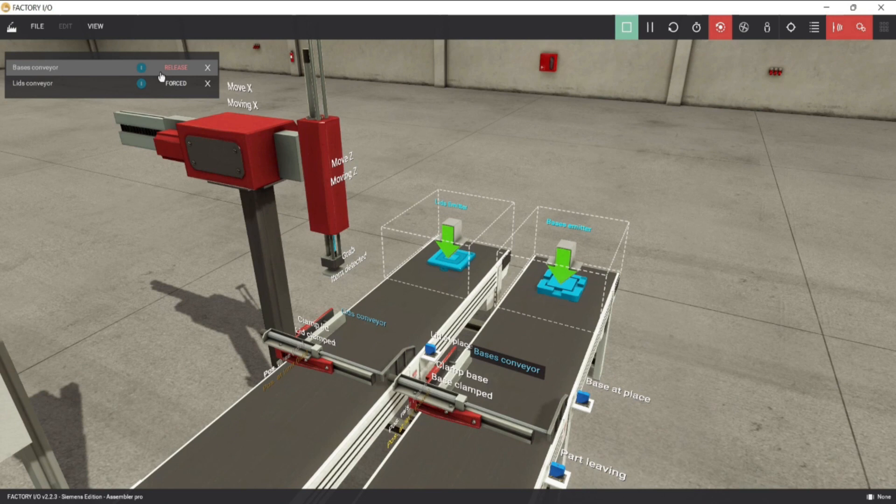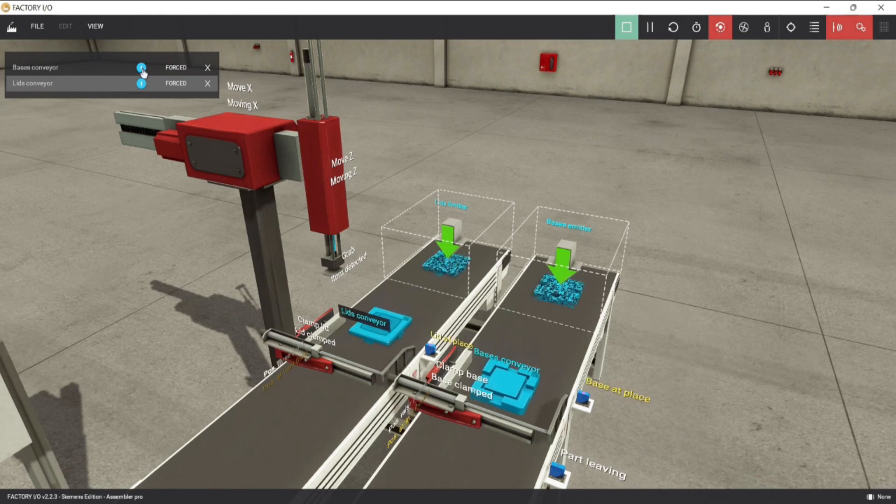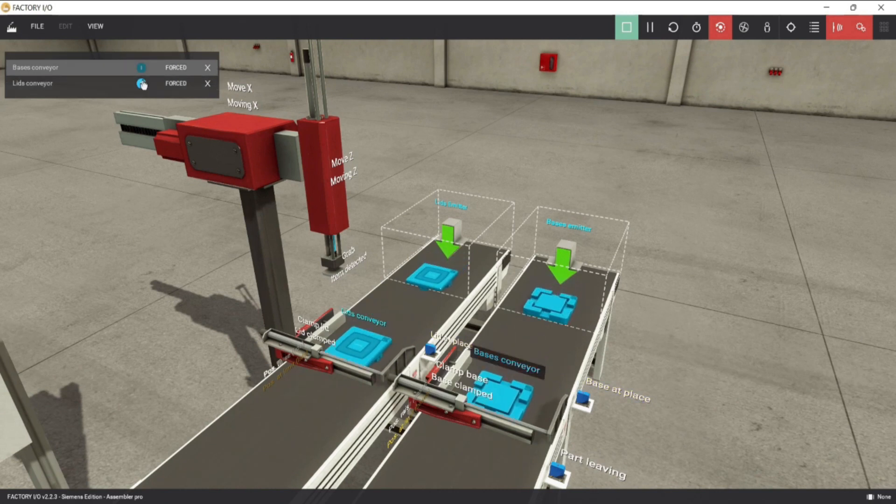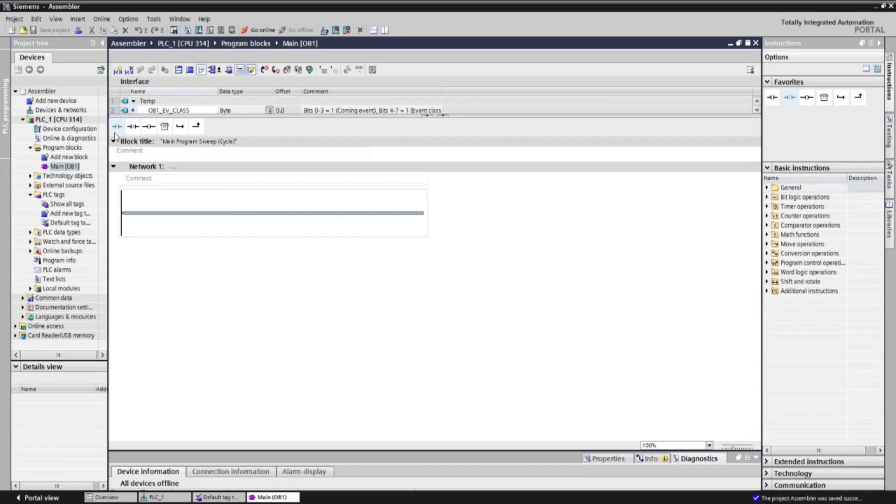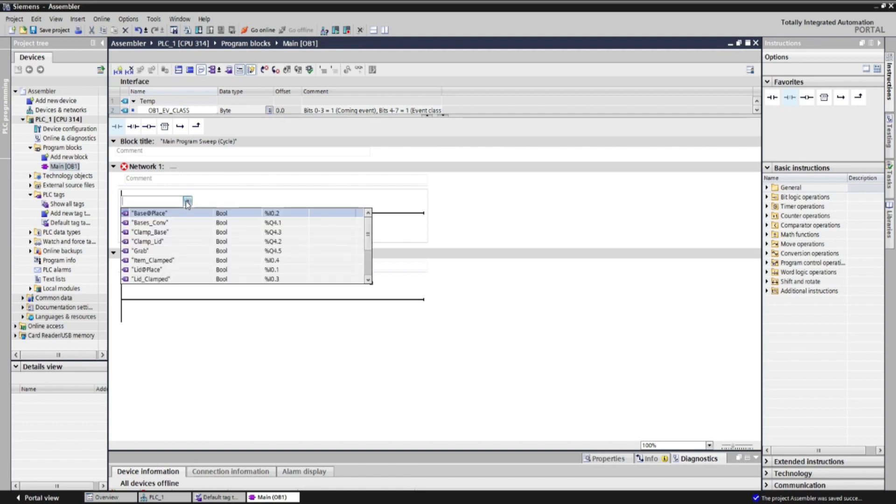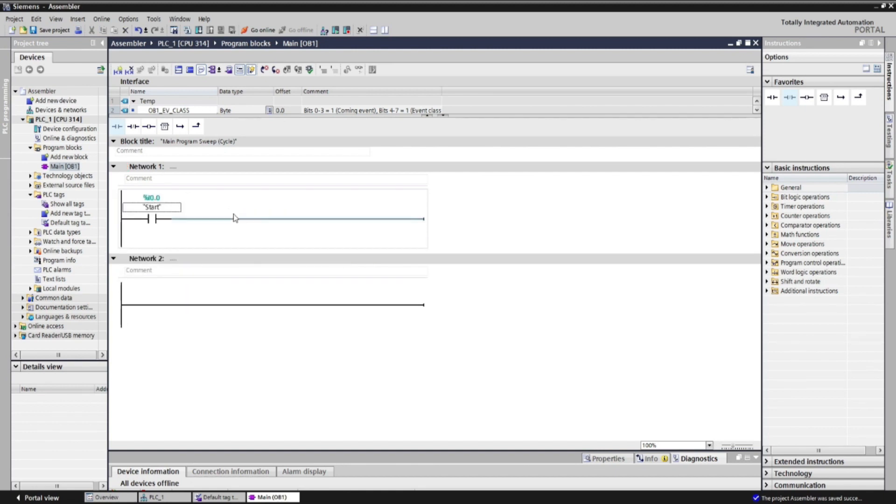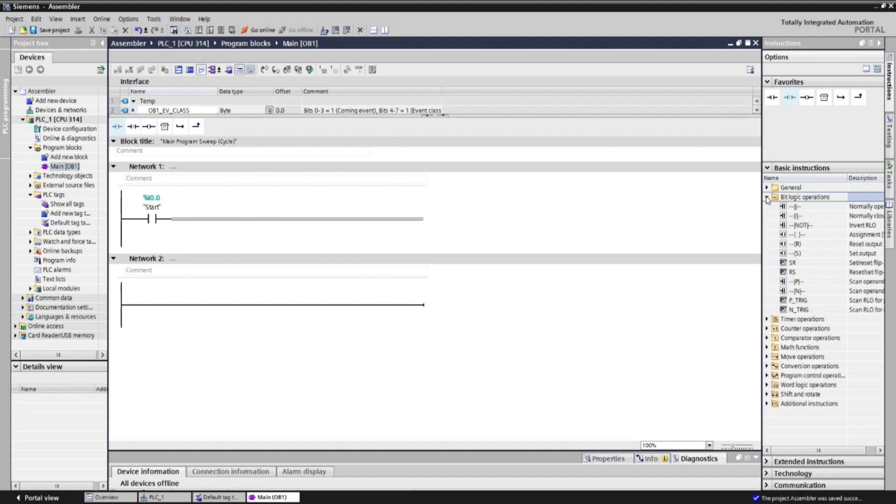Looking back at the operation, when the unit starts, lid and base conveyor will run at the same time. On our first network, let's insert a normally open contact, and address it as start. When start energized, 2 conveyors will run, so let's add 2 set functions, and address them as lid and base conveyor.